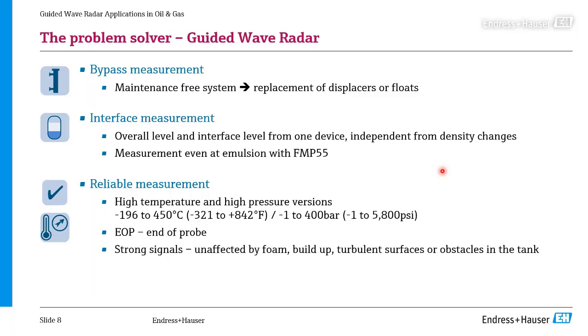We have a so-called end of probe signal evaluation, which Rob will tell you a little bit more about. And in general, we have a strong signal because the signal is guided along the probe, and this makes it stronger, and you don't lose too much of your signal strength. And this helps us when we talk about foam in a process, when we have build-up, or if you have turbulent surfaces or also obstacles in the tank. And last but not least, there is something called the gas phase compensation, and I will tell you more about this later on. So these are the pros for guided wave radar.